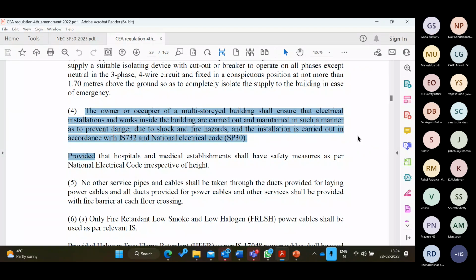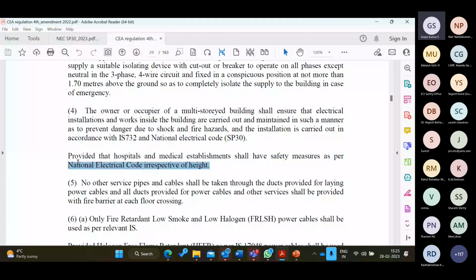So this regulation, as I said, the final version will most probably be published within a month. Recently, in one of the seminars in Delhi, the Central Electricity Authority officials informed that the English version is approved and they are translating it to Hindi, probably in a month. Now, this regulation gives a very clear indication that for buildings more than 15 meters in height, NEC is mandatory, or IS 732 is mandatory. Similarly, hospitals and medical establishments shall have safety measures as per the National Electrical Code, irrespective of height. So, very clear.